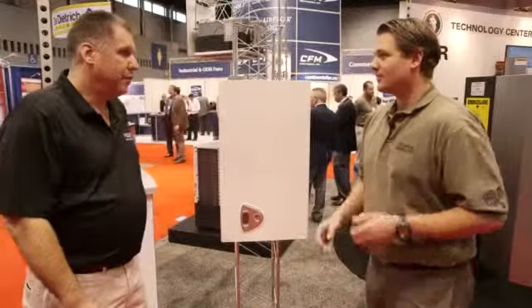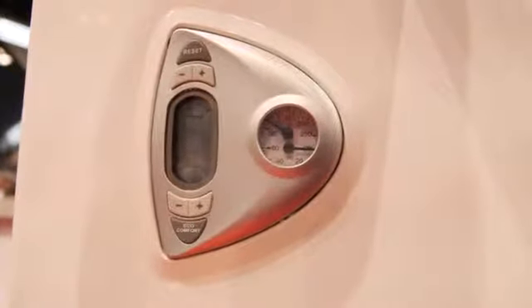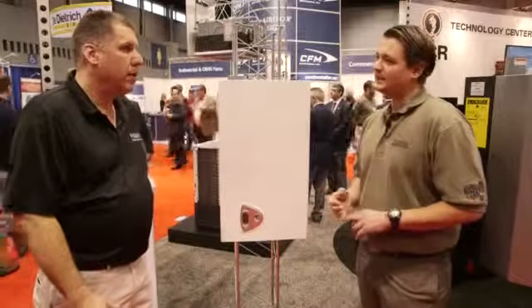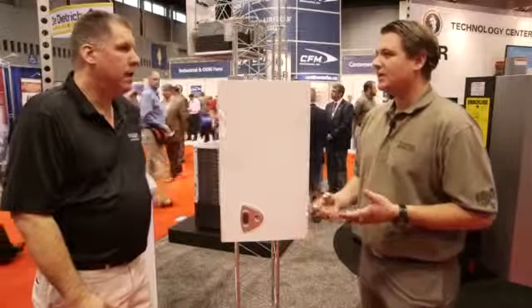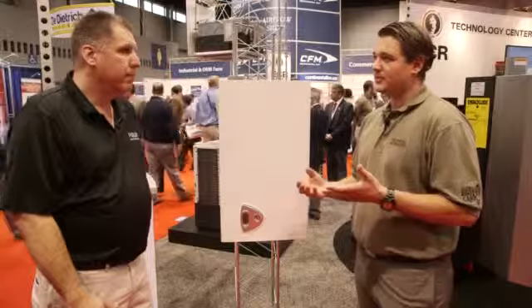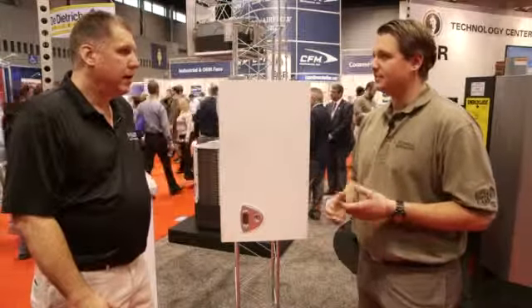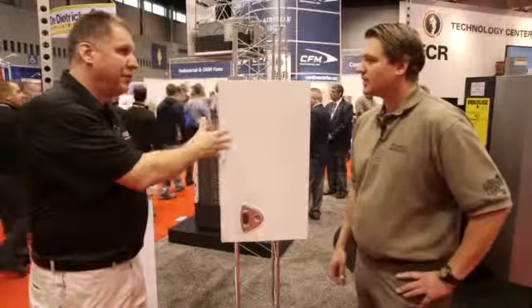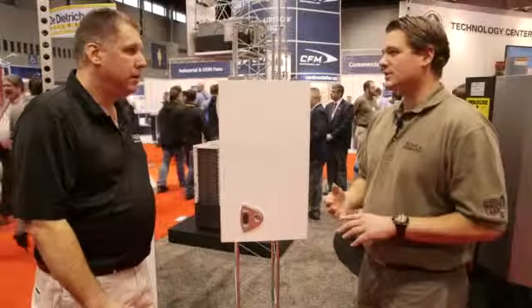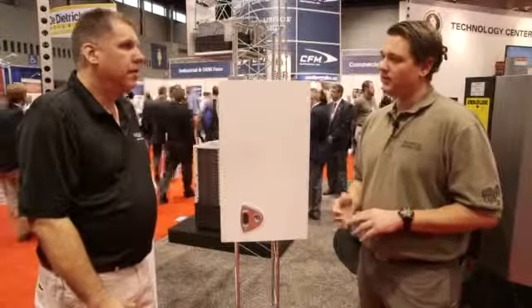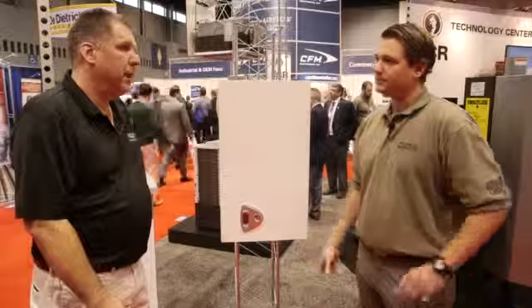I see. So this does both space heat and domestic heat? Correct. Yes, it's going to do both. You're going to get 3.6 gallons a minute at a 70-degree rise. Right. And if you wanted to go up to 6.3 gallons a minute, you get about a 40-degree rise out of it. I see. So does this come in different sizes, one size? We have a 150, which is our Combi, and then we have two heat-only versions, a 100 and a 130. I see, I see.